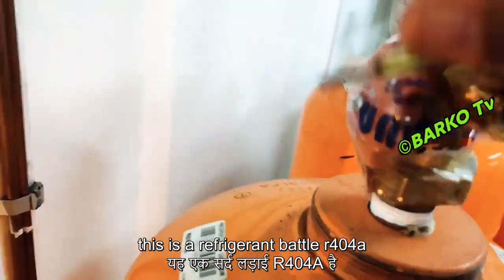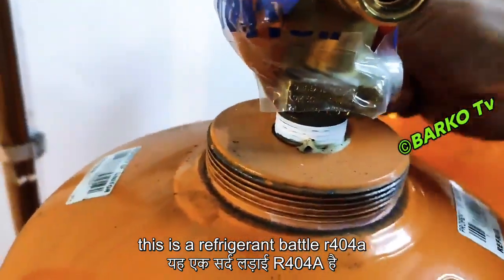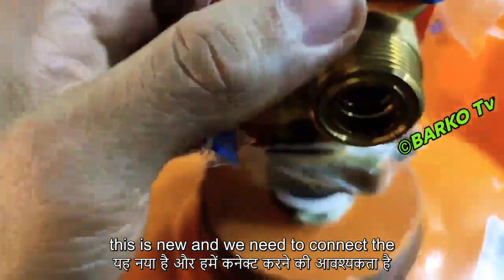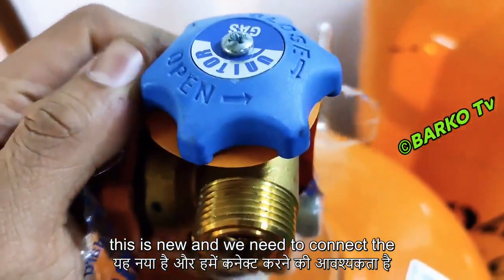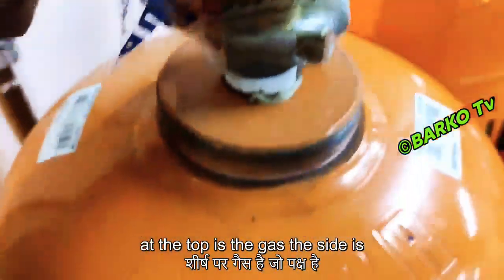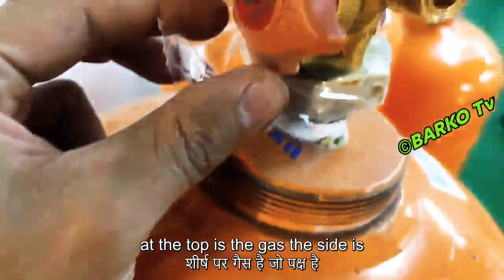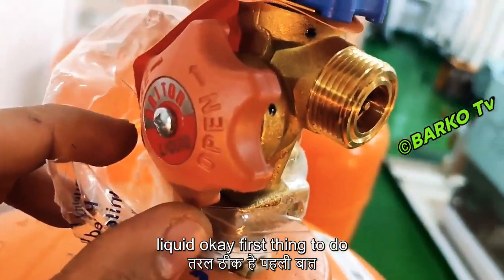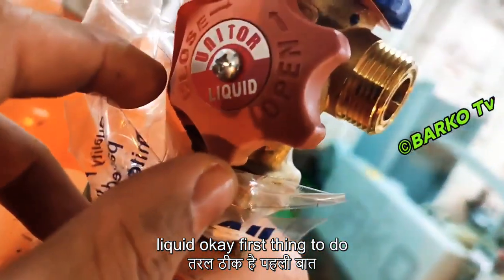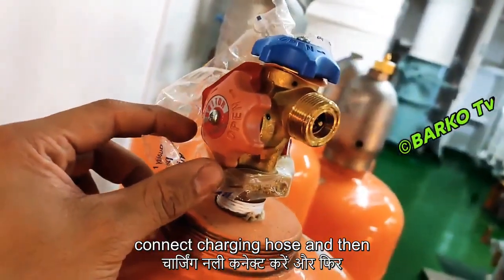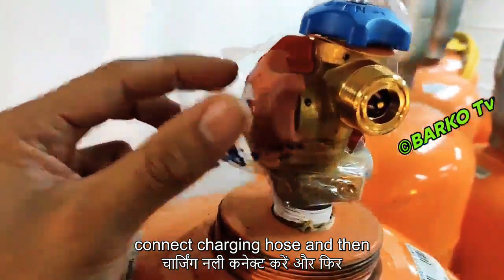This is our refrigerant bottle R404a. This is new, and we need to connect the charging hose. At the top is the gas, at the side is liquid. Okay, first thing to do, connect charging hose, and then you need to bleed.